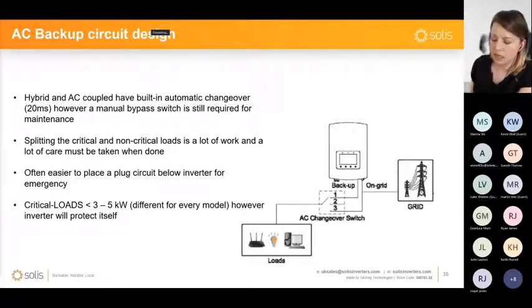I haven't mentioned this, but it's quite okay, and quite usual, to have these systems installed without making any use of the backup port. That can be left unconnected and unattended. So it's not mandatory. Not all customers require their critical loads to be powered when there's a power outage, because this will also involve extra costs, as there's a lot of work. Those critical loads need to be split, disconnected from the grid, put on a separate circuit, and connected to the backup port.